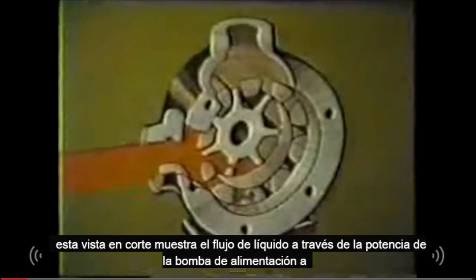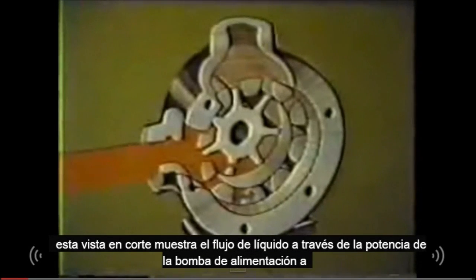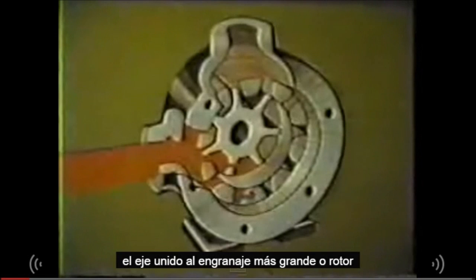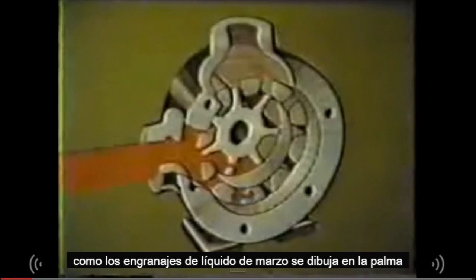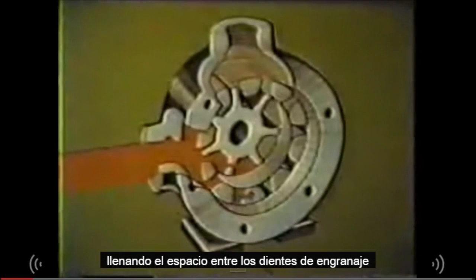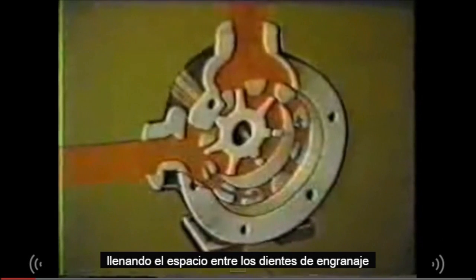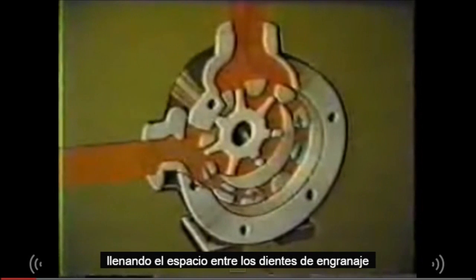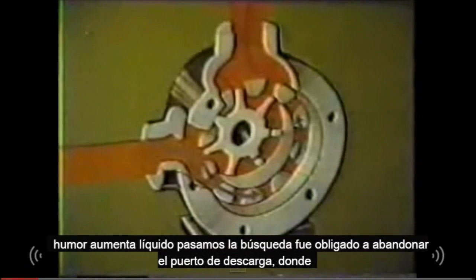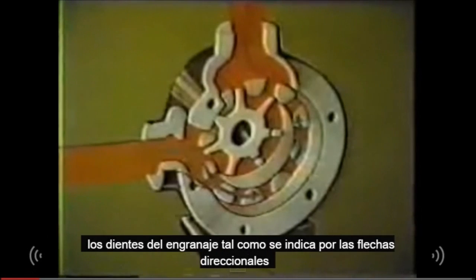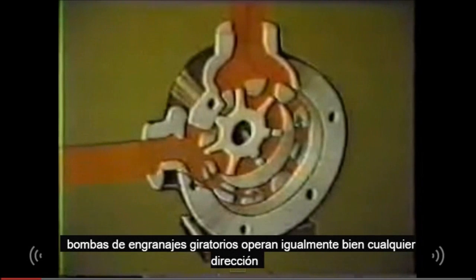This cutaway view shows the flow of liquid through the pump. Power is supplied to the shaft attached to the larger gear or rotor. As the gears unmesh, liquid is drawn into the pump, filling the space between the gear teeth. The liquid moves smoothly past the crescent and is forced out the discharge port by the meshing of the gear teeth, as indicated by directional arrows. Rotary gear pumps operate equally well in either direction.